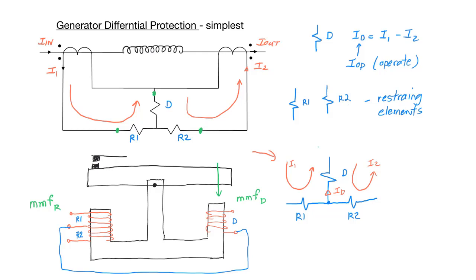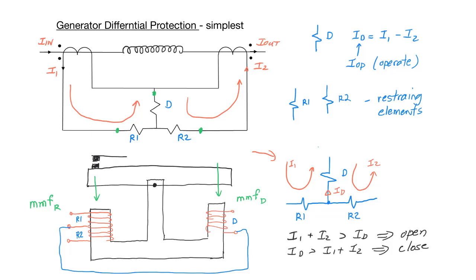This will trip a circuit breaker. If, on the other hand, the magnetomotive force from the restraining elements is greater than the magnetomotive force from the differential element, the contacts will be held open and the relay will not operate. In summary: the restraining currents I1 and I2 act to keep the contacts open; the differential current acts to close the contacts. If the difference force is greater than the restraining force, the contacts will close and a circuit breaker will operate to take the faulty equipment out of service. That wraps up this video, which provided a brief introduction to differential protection and the differential relay.